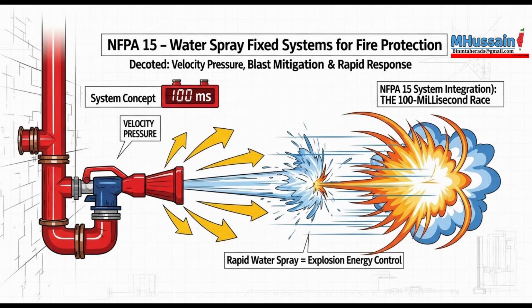Okay, direct measurement. But for all NFPA 15 systems, including standard speed ones, the acceptance discharge test in 10.4.3.2.3 includes a step that sounds, well, counterintuitive, the throttling test. Oh yes, the throttling test. It is crucial, even if it sounds backward at first.